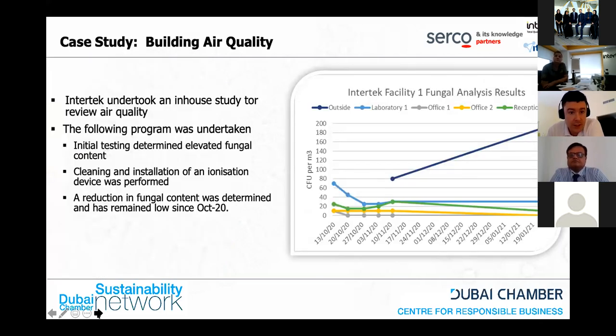We undertook a study in-house within several of our facilities in the UAE. We set some benchmark testing at the beginning to see where the air quality started, then did some cleaning as well as installation of some ionization devices. What we've seen is that even with changing air quality outside, depending on seasons, wind strength, and any construction in the surrounding environment, these types of devices can be successful where the environment was clean. What we've seen in other facilities is that the cleanliness of the system at the beginning is hugely important to the operational quality of some of the hygiene devices. So if you don't start with a clean canvas for your AC system, it's very difficult to install ionization, HEPA, or UV devices that will be effective.